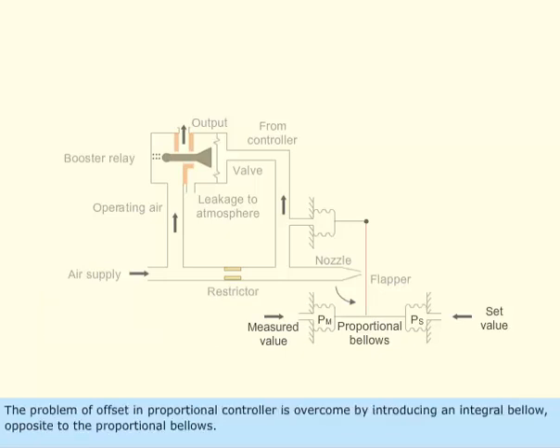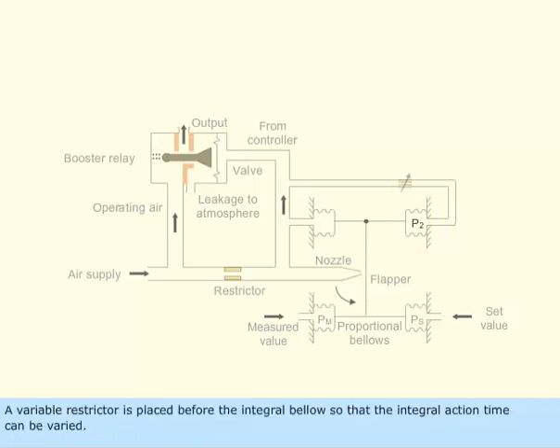The problem of offset in proportional controller is overcome by introducing an integral bellow, opposite to the proportional bellows. A variable restrictor is placed before the integral bellow so that the integral action time can be varied.